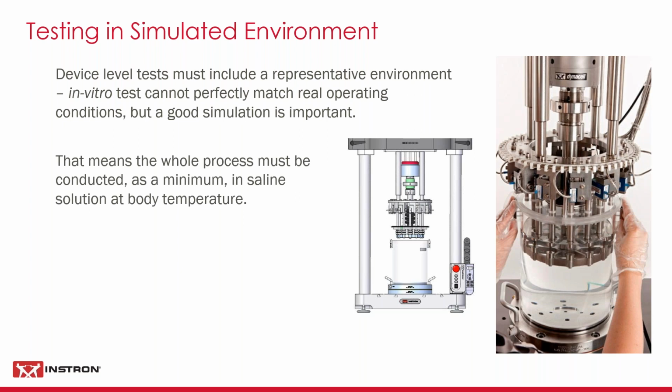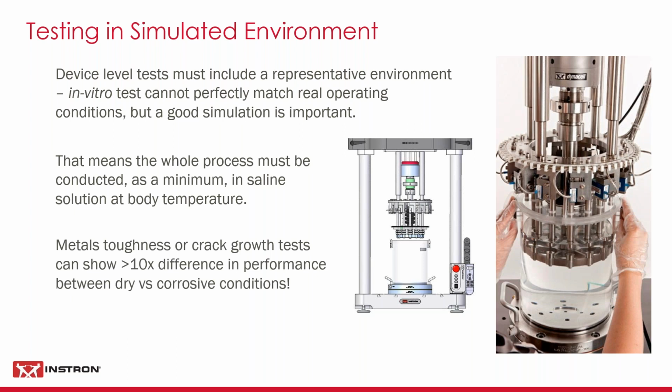So that means the whole process has to be at the right temperature, and it's really about getting the right corrosion chemistry going on around the surface. Now we hope, well, you as device developers might hope that you won't really get any measurable corrosion, but you've got to prove it.